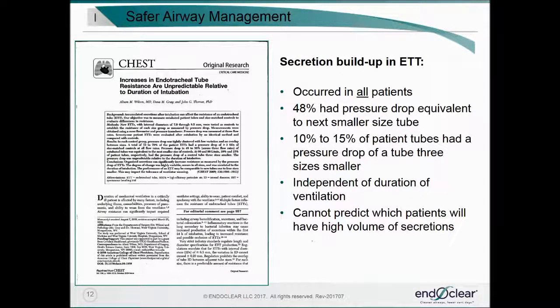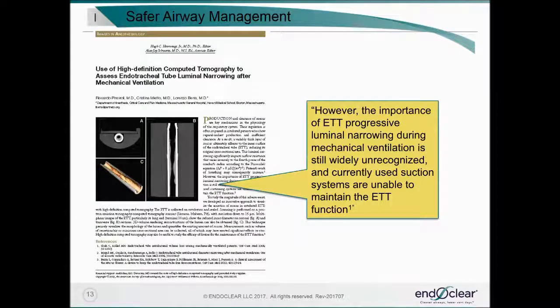This article in Chest out of West Virginia University in 2009 shows us that secretion buildup in endotracheal tubes is common and can result in marked increases in airway resistance. These researchers also found that obstruction can occur quite early and is not entirely predictable by patient characteristics. This article out of Massachusetts General Hospital used high-definition CT to confirm that endotracheal tube obstruction is common and widely unrecognized, and that current suction systems are unable to maintain endotracheal tube nominal function.